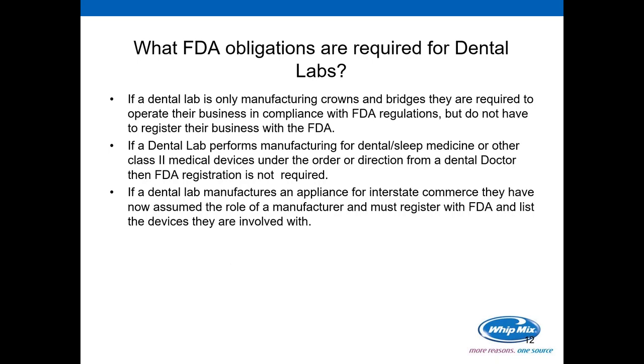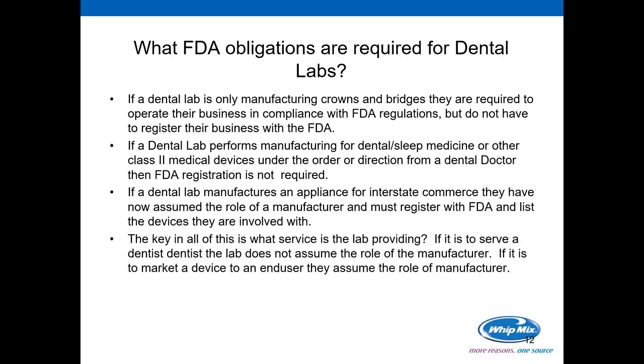If the dental lab manufactures an appliance for interstate commerce — in the case of Whip Mix, like marketing our VeriSplint — you have now assumed the role of the manufacturer. That means you have to list your facility and the devices you are selling with the FDA. The key in all this is what service is the lab providing. To sum it up, if it is to serve a dentist, the lab does not assume the role of the manufacturer. But if you are marketing a device to an end user on your own without the direction of a dentist, you have now assumed the role of a manufacturer.